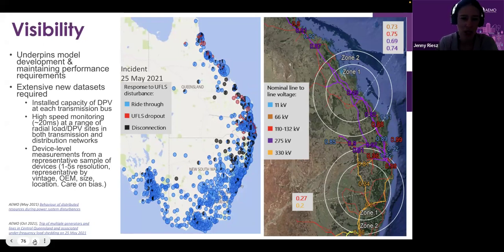The example shown here is a major incident on the 25th of May, 2021, in southern Queensland - you can see the red and black dots about halfway up the coast of Australia. We had multiple explosions at some coal-fired power stations that led to voltage dips on the grid. On the right are the minimum per-unit voltages recorded across different levels of distribution and transmission. The bubbles on the left show the amount of PV responding in different ways: blue systems riding through, which is desired; black systems disconnecting, which is undesired because it exacerbates a severe under-frequency event; and red bubbles are ones disconnected by under-frequency load shedding, triggered by the severe event, which in those places also disconnected distributed PV along with load. So we have another piece of work looking at how to improve under-frequency load shedding design so it doesn't trip off generation in an under-frequency event.